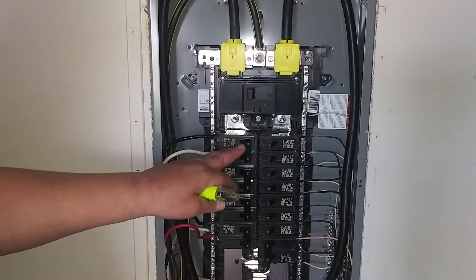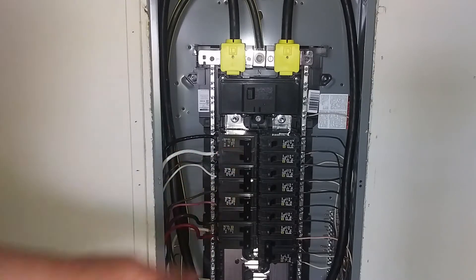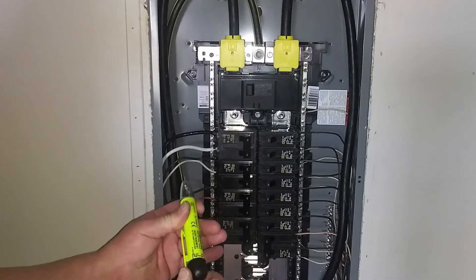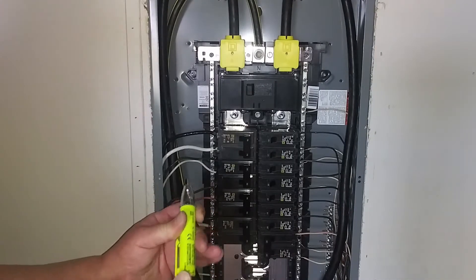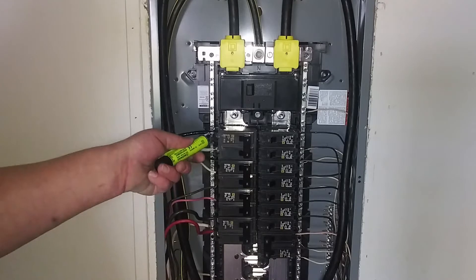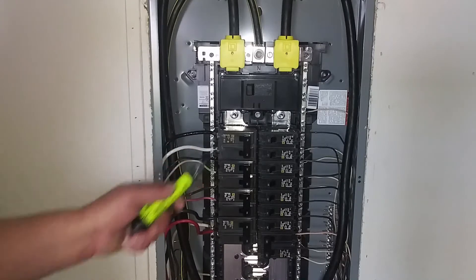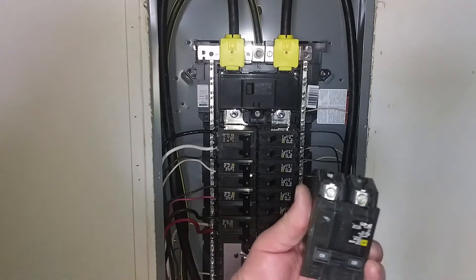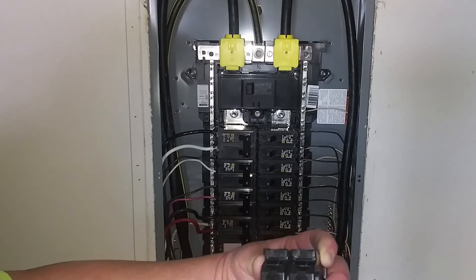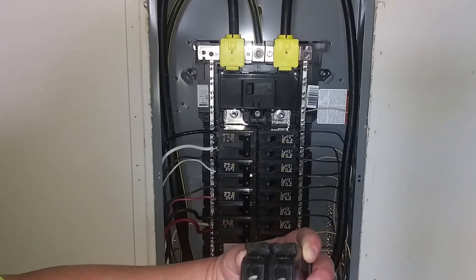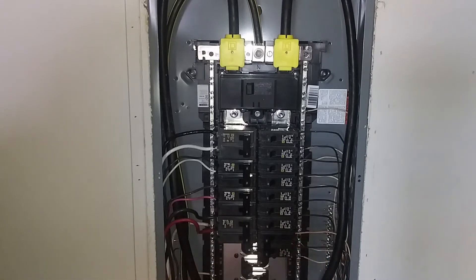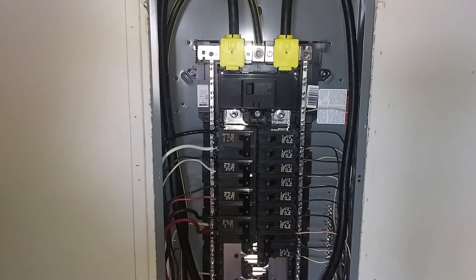And here's our double pole breaker. Now, I do have a test light. I'm going to take my test light, turn it on, make sure there's no power to it. Then I've got these two screws, and then you open up these little clamps. Go ahead and unscrew those a bit. It'll make it a little bit easier on you when you put it in. Just be careful not to screw them the whole way out.